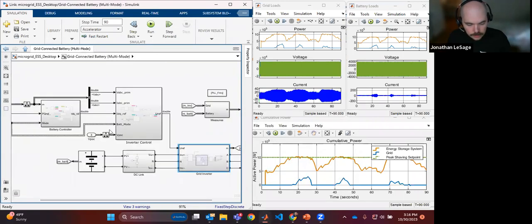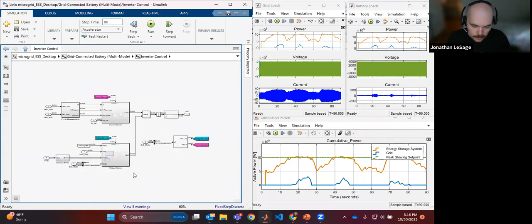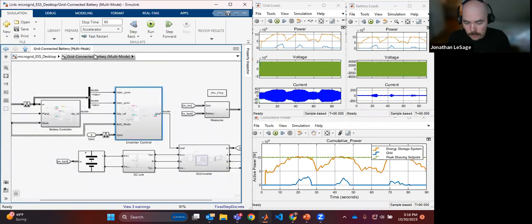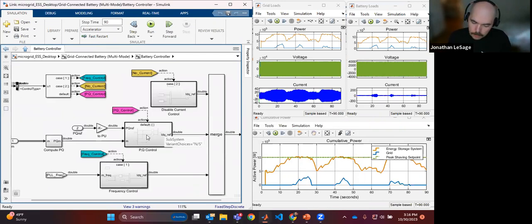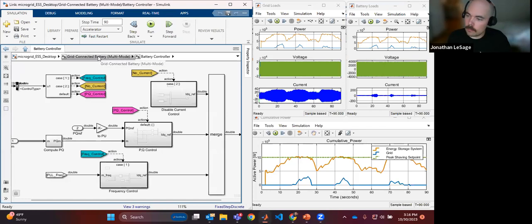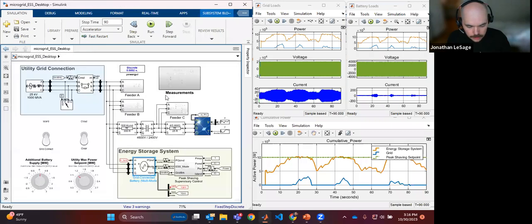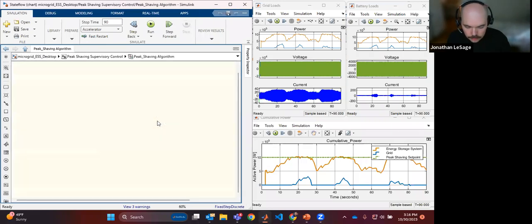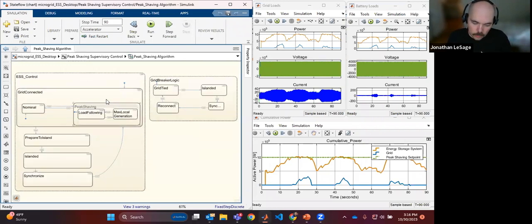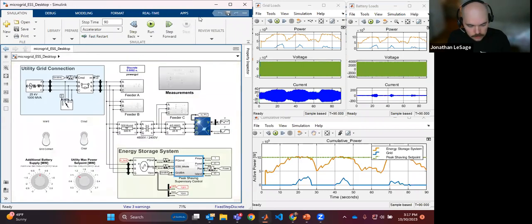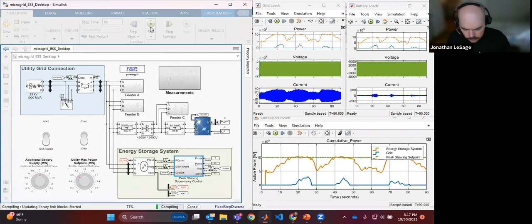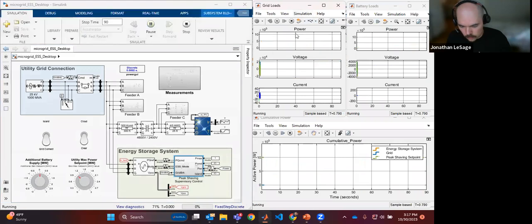Going up to the next level, I'm looking at active and reactive power control and frequency regulation. At the very highest level, we have a supervisory energy management system — in grid-connected mode we might have peak shaving or load following, and we also have different modes of operation if islanded. This is a full electromagnetic transient simulation, recording different data points including power draw from the grid, active and reactive power, three-phase waveforms, and battery data.